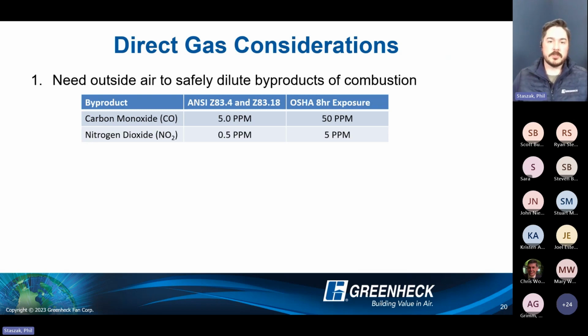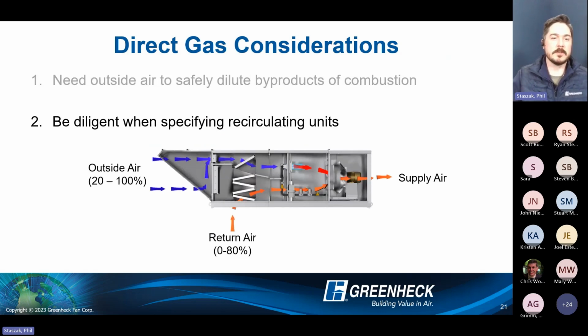and walk away completely fine. So that should hopefully set the story straight: what we are allowed to bring in is an extremely clean burn, and again, heavily diluted with outside air. You can be exposed to 10 times greater than what that unit is actually bringing into the space before it's being exhausted out in the first place. So just to set that story straight.